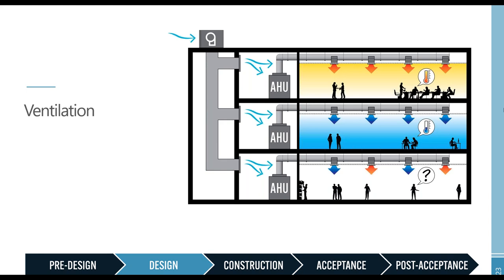So for those that aren't typically involved in controls, controlling to just below the duct pressure rating is fairly unusual. You usually want to have a test and balance contractor determine the appropriate set point for you so that you're providing the optimal amount of air. But seeing the sequence, some alarm bells went off.